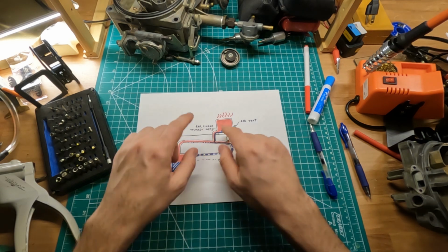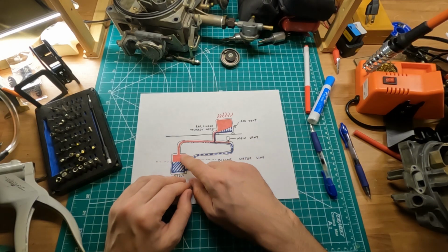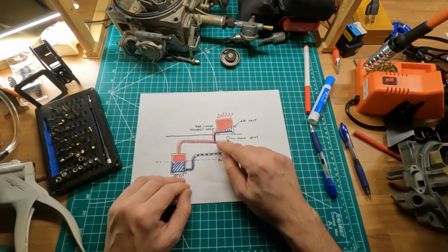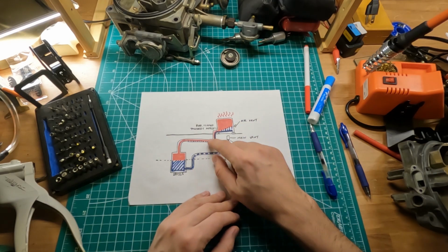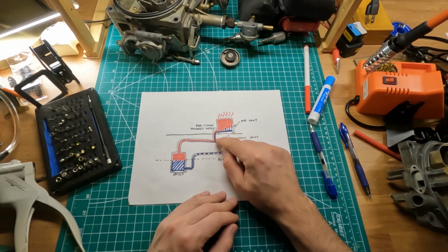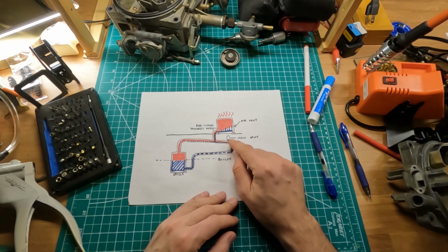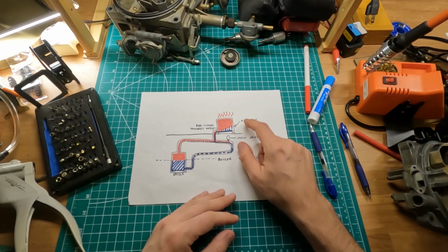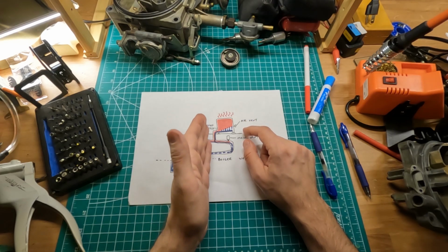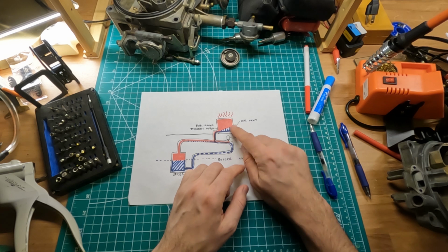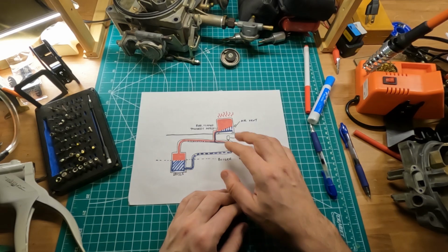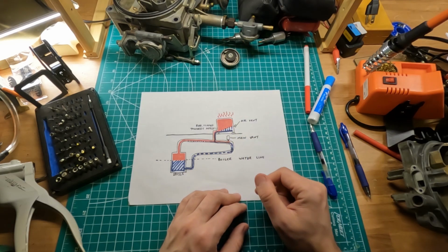Now, again, there's a bunch of different codes that I'm going to talk about in just a second. When the steam gets trapped in the main pipe, then the steam, by definition, wants to go somewhere and starts going up the risers into the radiators. And the radiators, just like the main pipe, have a vent. So the radiator has an air vent as well. Again, steam pushes the air out of the radiator through the air vent, and when the steam hits, the air vent closes, and then the radiator stays nice and warm and starts releasing heat into your room.